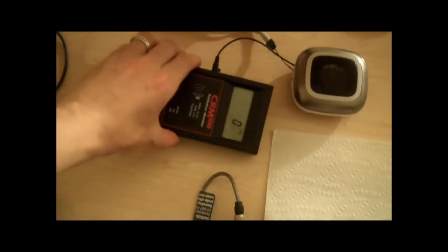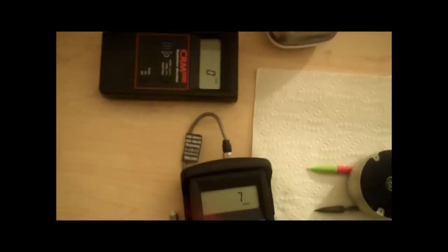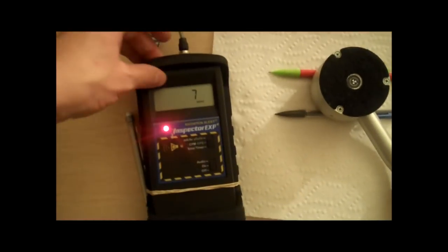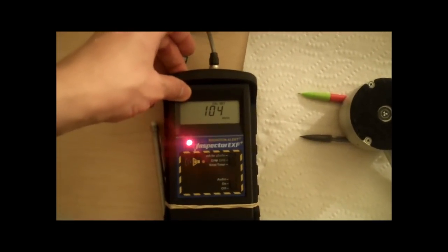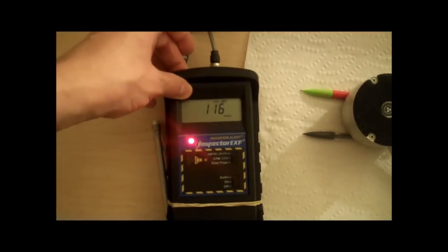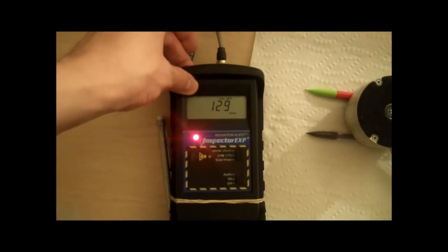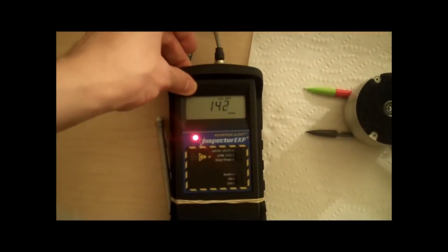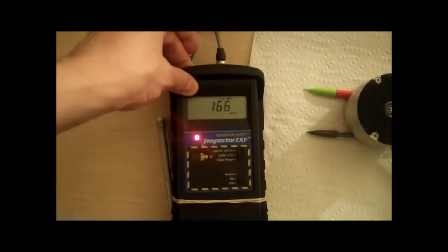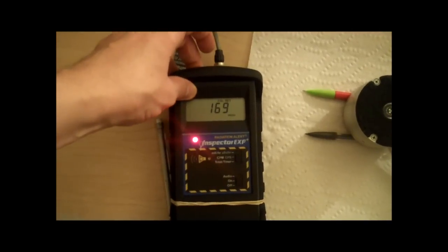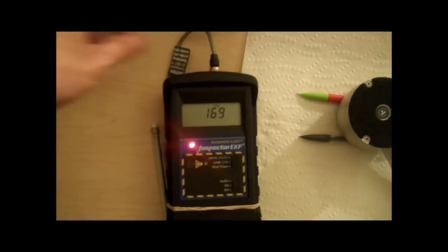Every Geiger counter is calibrated differently. Like this guy right here, same type of thing as this one. It has the same basic thing, option 7 and so on. If you have an old CDV 700, you're going to be going at it with a screwdriver. They're all a little bit different. Anyway, we hit the set button, so we go into option 7. And we're going to calibrate this thing. I think I know where to go with this, because I already tried it earlier. 169 should be the right cal setting. Boom, boom, boom. I think that 169 is correct. Press the set button, let it go.